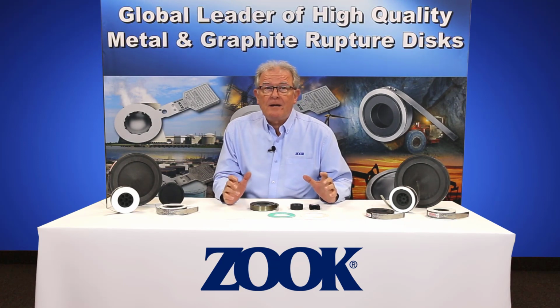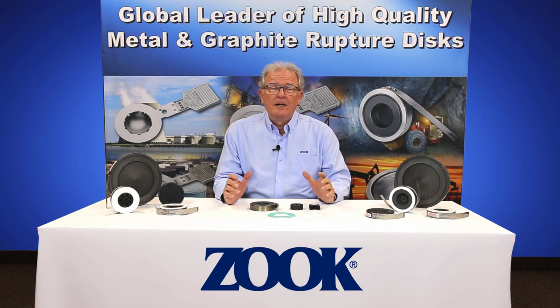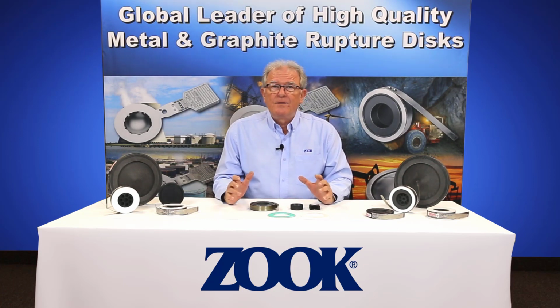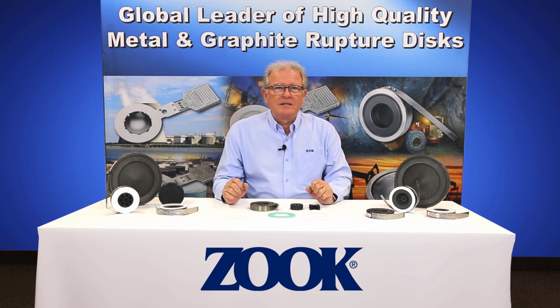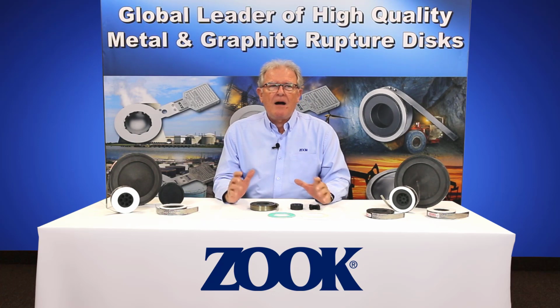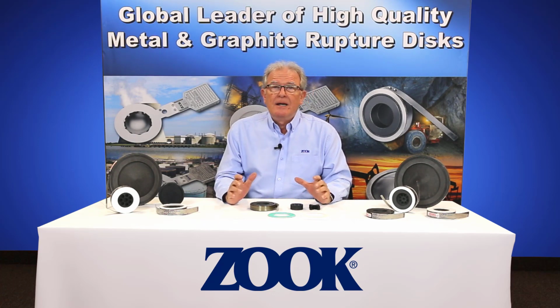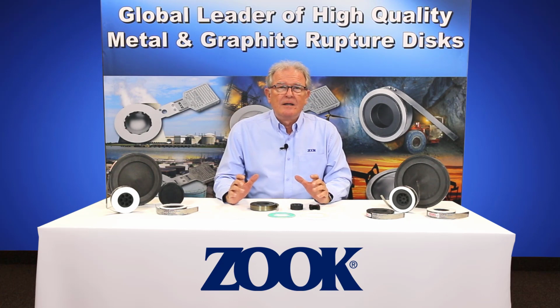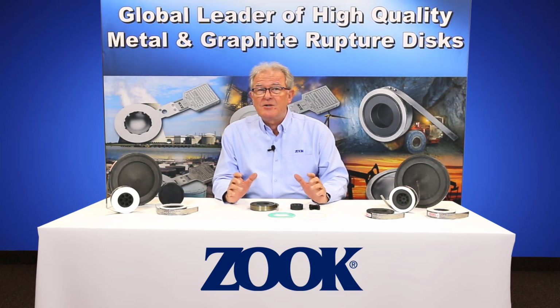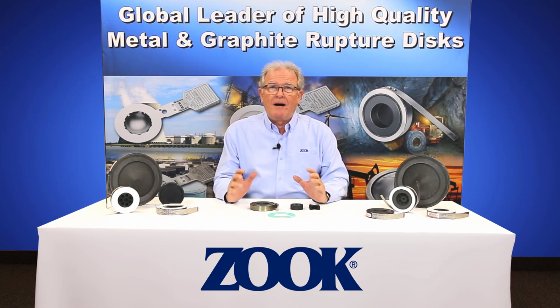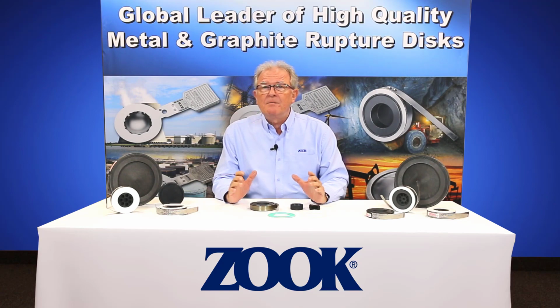So with phenolic resin impregnated graphite, we now have created a low tensile strength material from which we can make graphite rupture discs. Graphite is a highly corrosion resistant material and can be used where there are aggressive fluids present. Graphite is an inert material that does not give ion contamination. That's I-O-N, ion contamination, and has great temperature stability compared to metals.